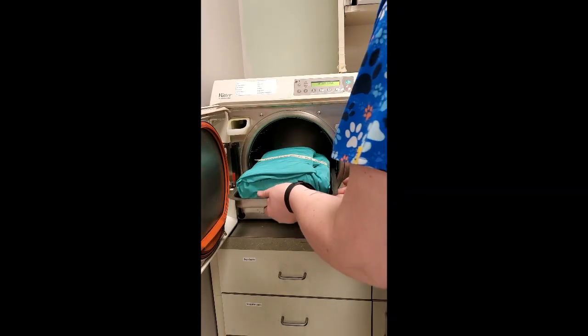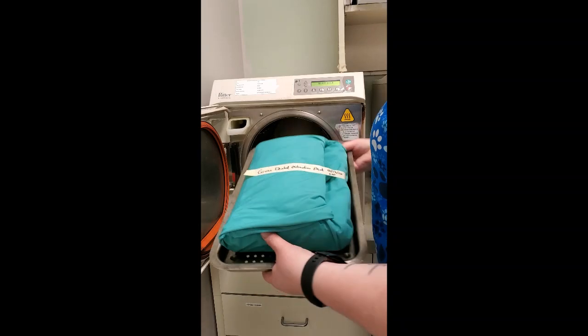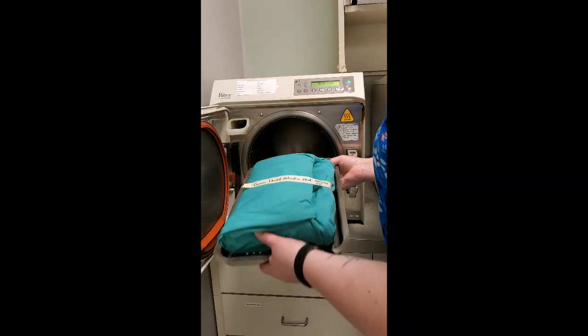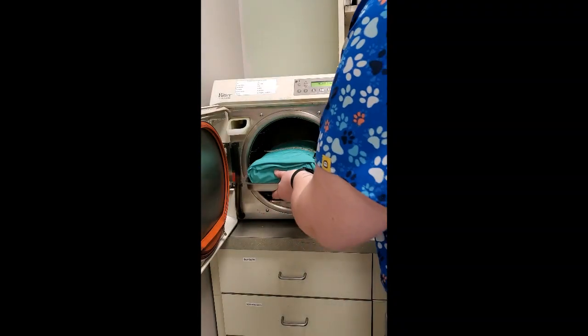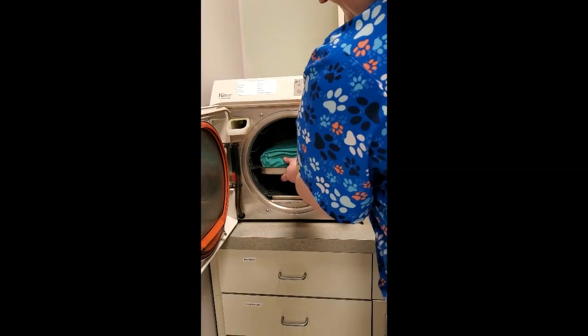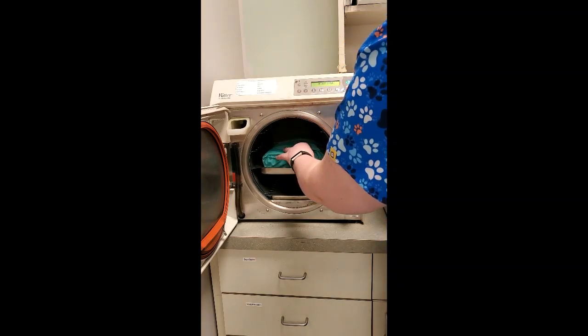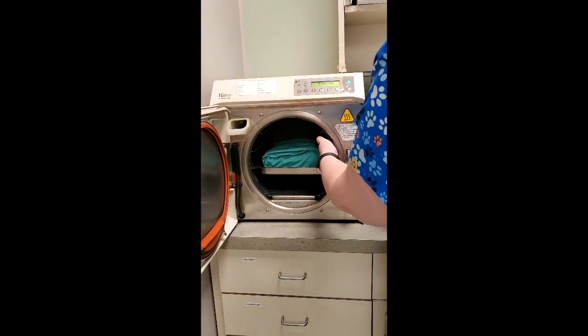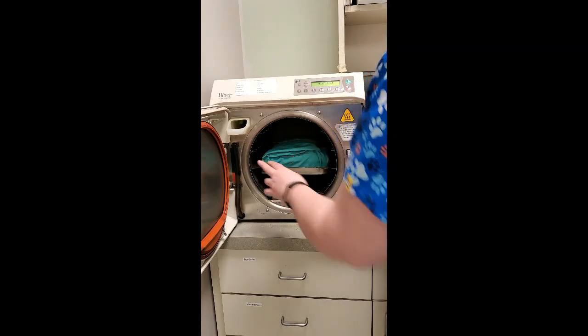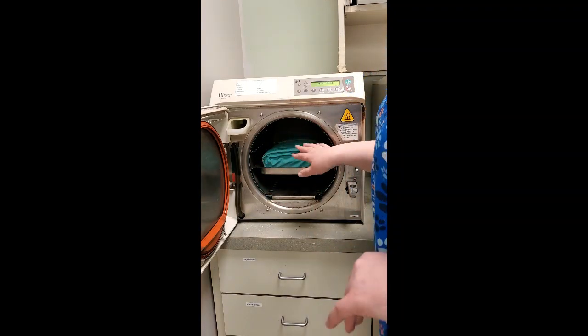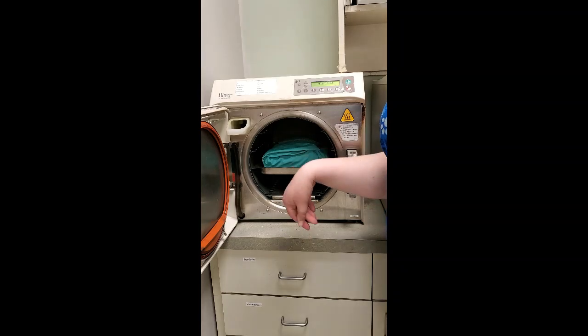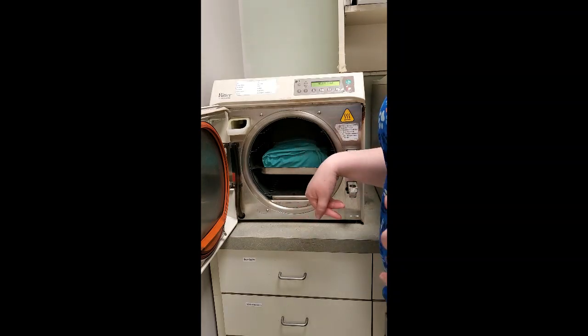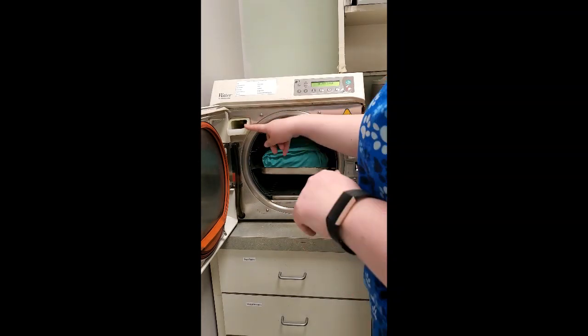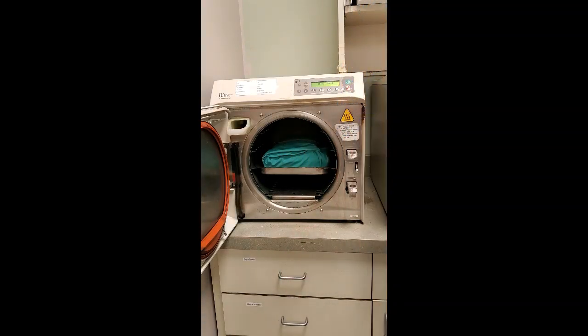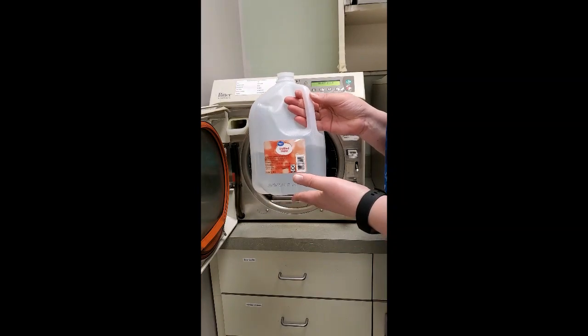So for this, you can see that it is on the tray. There's space around it on the sides. It's not touching the side of the autoclave. We're not going to stack any packs on top of it or anything like that. If it needed more distilled water, we would add that up here just to show you. So we would use the distilled water.